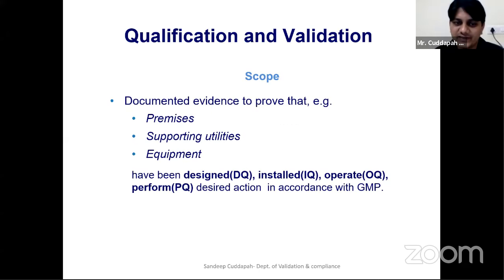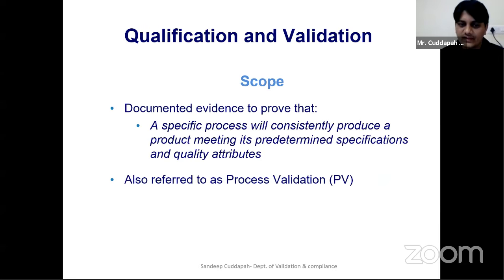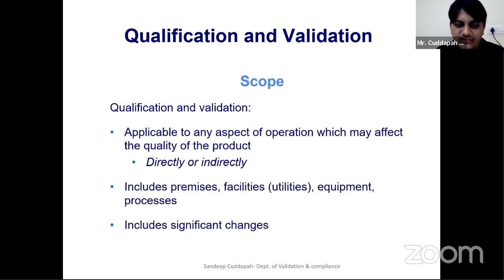Qualification and validation scope is not only limited to equipment, it is even for the supporting utilities. And if you are doing manufacturing in a facility, you have to do validation for that area, for the facility premises also. The main thing after performance qualification is that you will do performance validation. As I told you, this performance validation is to verify the equipment's suitability to your process, which you will decide in the case of process validation.